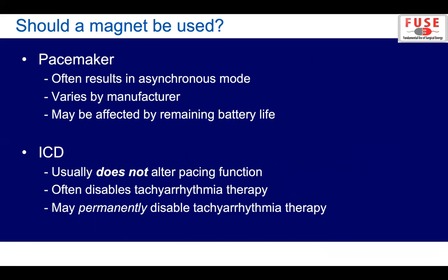The next question: should a magnet be used? Certainly it's often simpler than involving your cardiology team or an industry rep to reprogram the device. For a pacemaker, it often results in an asynchronous mode. However, this varies highly by manufacturer, and the exact mode may be affected by the remaining battery life. For an ICD, it's very important to keep in mind that usually a magnet will not alter a pacing function. So with a combined pacemaker ICD, it will often disable the tachyarrhythmia therapy but not affect the pacing function. There have been cases where the tachyarrhythmia therapy was permanently disabled. This is again rare and occurred quite some time ago, but keep in mind that anytime you're messing with these devices, there can be unexpected sequelae.